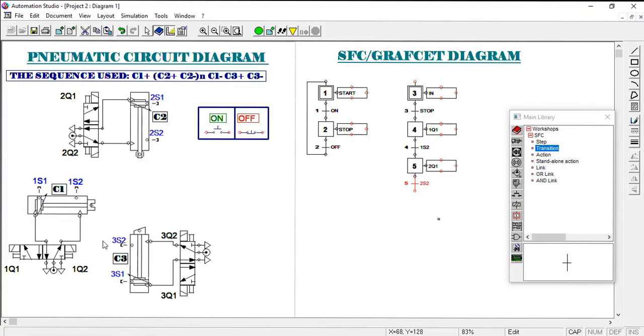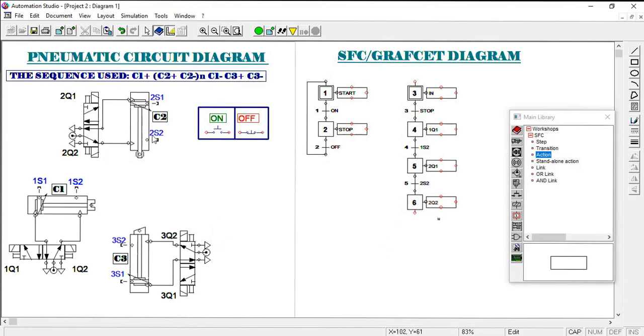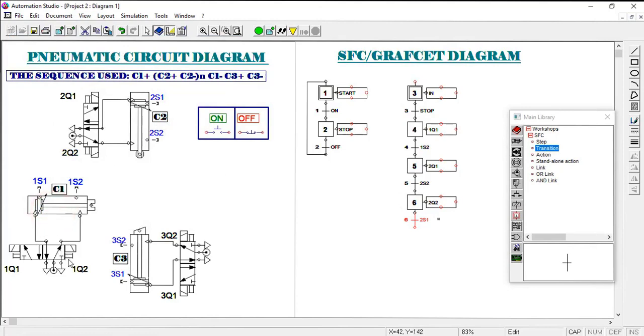When 2S2 is reached, it's time to retract cylinder two back after the stamping operation. We add step six with action 2Q2, which causes the piston to retract. When it goes back, it is detected by sensor 2S1, which becomes the next transition, and this is used to change position for the next operation.